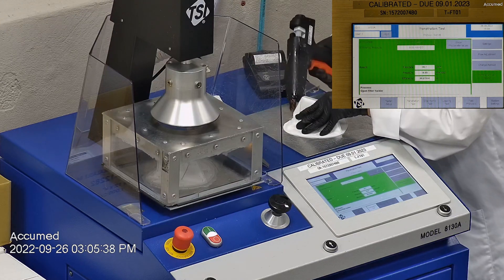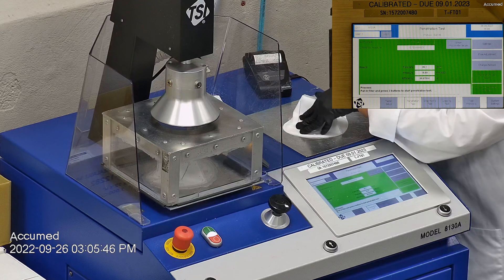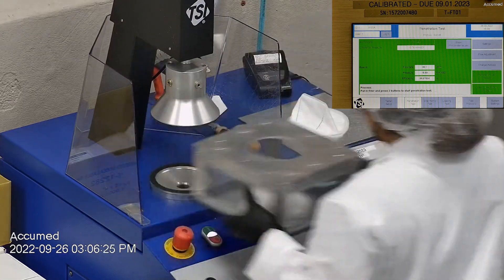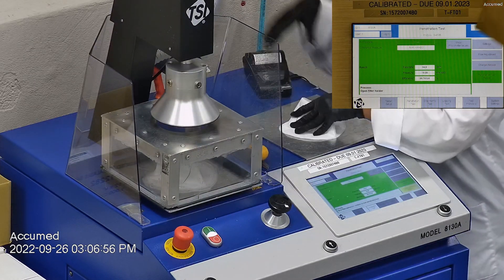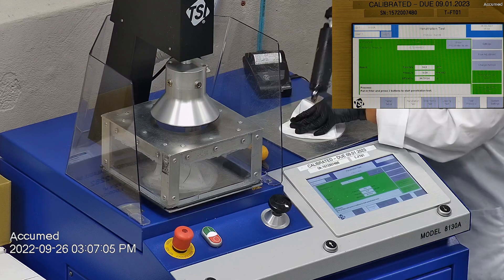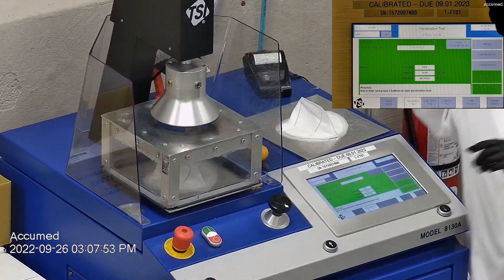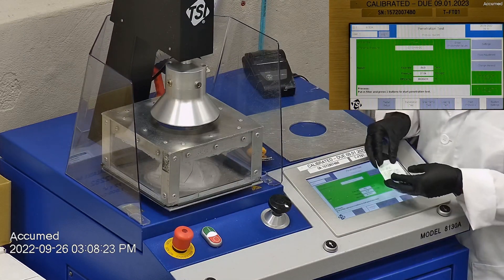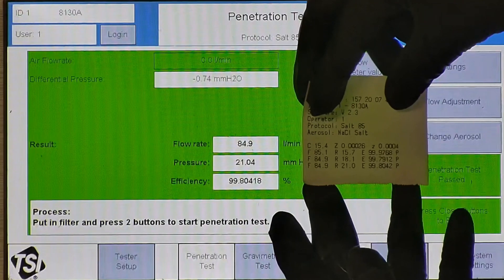The first sample had a filtration efficiency of 99.97% and a pressure drop of 18.1 millimeters of water. The second sample had a filtration efficiency of 99.79% and a pressure drop of 18.1 millimeters of water. The last sample had a filtration efficiency of 99.80% with a pressure drop of 21.04 millimeters of water.